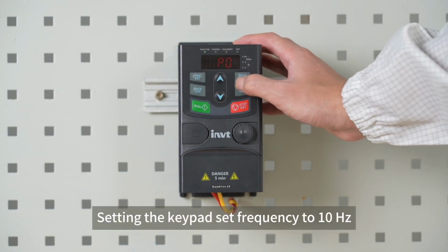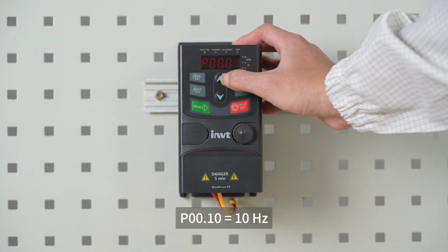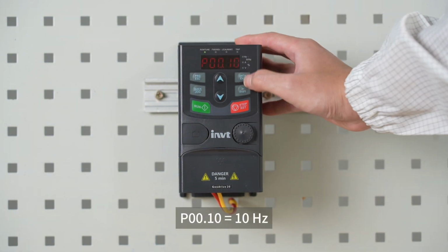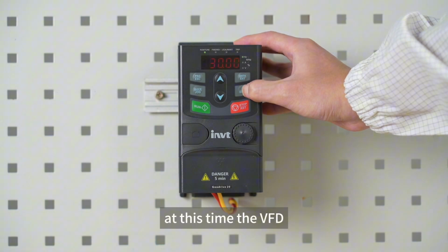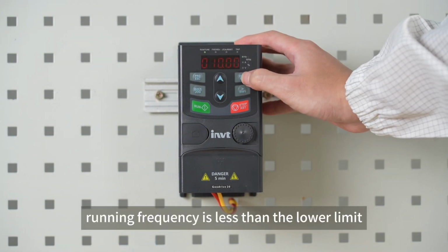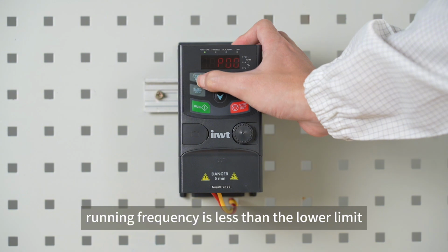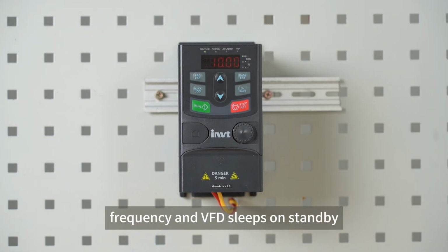Setting the keypad set frequency to 10 Hz, P00.10 equals 10 Hz. At this time, the VFD running frequency is less than the lower limit frequency and the VFD sleeps on standby.